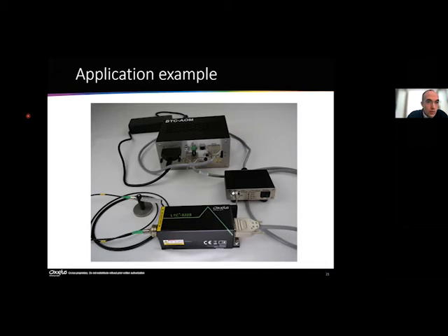Yes, so I have a question here concerning the heat sink. Obviously my table was not an optical table, but if you fix the laser head to a standard optical table, then you wouldn't have to use the heat sink.